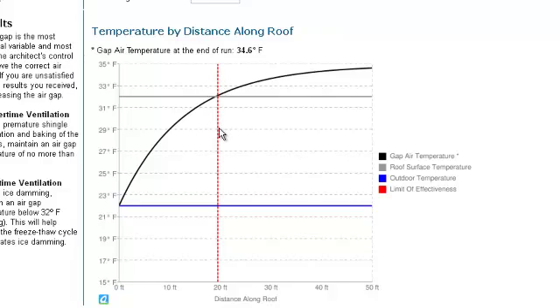Now, where these lines intersect is where we're going to have to focus. You'll notice the red line here, that's the limit of our effectiveness, and that ends at 20 feet. So what that's saying is that we'll have no problem for ice damming up until we reach 20 feet, when the air gap temperature remains below freezing.